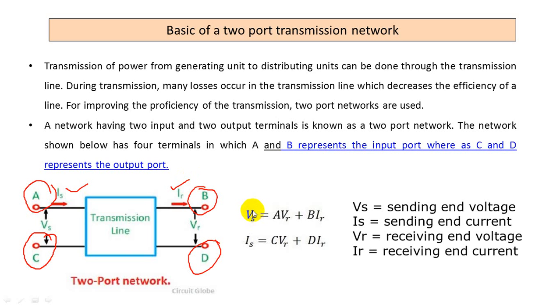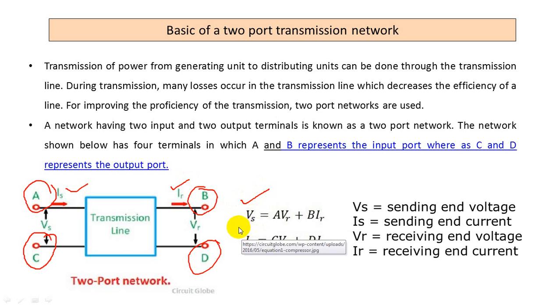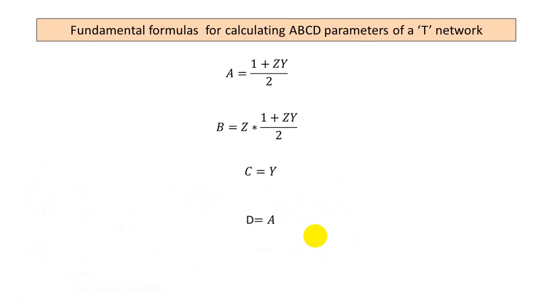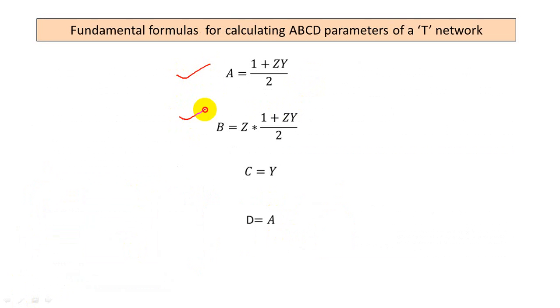The basic equation is very important: VS = A·VR + B·IR, giving the sending end voltage in relation with the receiving end voltage and current. Similarly, IS = C·VR + D·IR gives the sending end current. This is how VS and IS can be calculated. These formulas are derived and can be taken from your transmission and distribution network theory. These four parameters are completely different for a PI network and a T network.